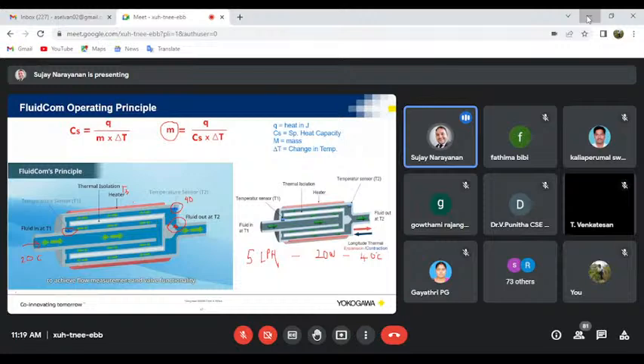Let us say the power in this case becomes 40 watts, and the temperature required is 50 degrees Celsius. Now what happens is it tries to open more. When it requires 40 watts, it draws more power and heats up more, and once it is heating more, its expansion is opening the valve more. And suppose somebody wants to give 1 liter per hour, so it is continuously adjusting.